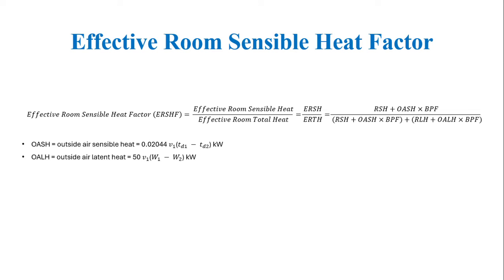The next factor is the Effective Room Sensible Heat Factor, ERSHF. The ratio is effective room sensible heat divided by effective room total heat (ERSH / ERTH). To calculate the effective room values, we multiply by the bypass factor: ERSH = (RSH + OASH) × bypass factor, and ERLH = (RLH + OALH) × bypass factor. The same outside air sensible and latent heat formulas from the previous case apply here.